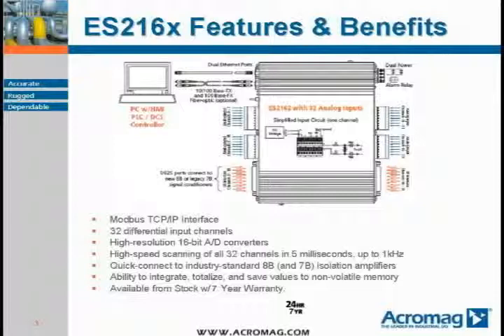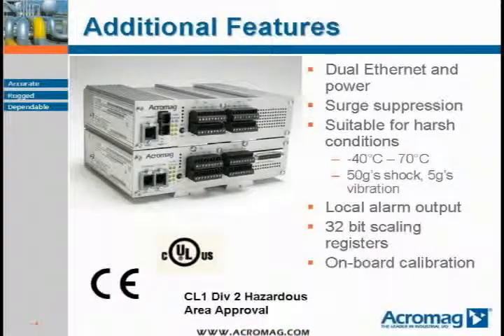The ES2161 and 62 have the ability to enable integration and totalization on all channels. This is ideal for flow applications relating to liquids, gas, or power, where users can read the instantaneous flow rates and totalize usages. Counts are stored to 32-bit non-volatile memory, which is retained if power is lost. In theory, integrating and totalizing flow rates at the remote I/O level can produce more accurate usage information over long-term measurements. Additionally, dual power and Ethernet ports provide for redundant communication and bumpless switching.